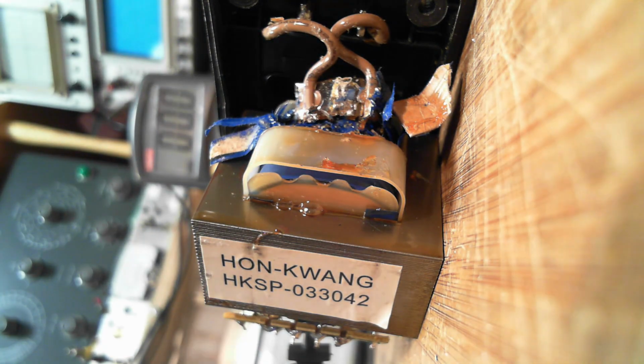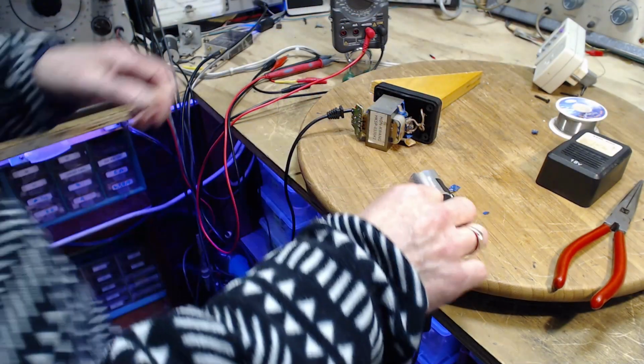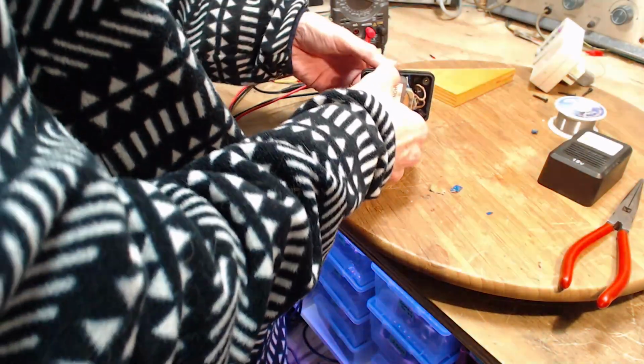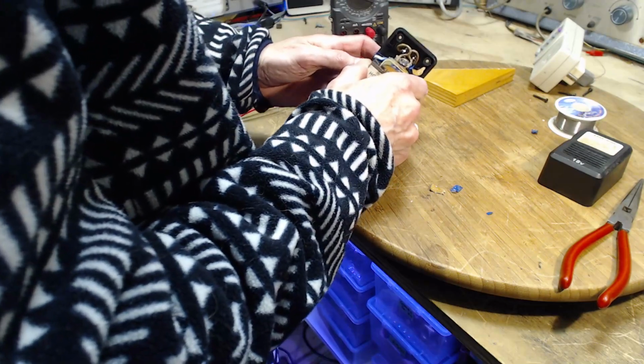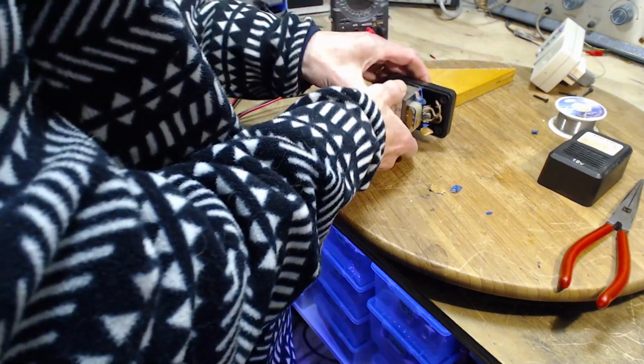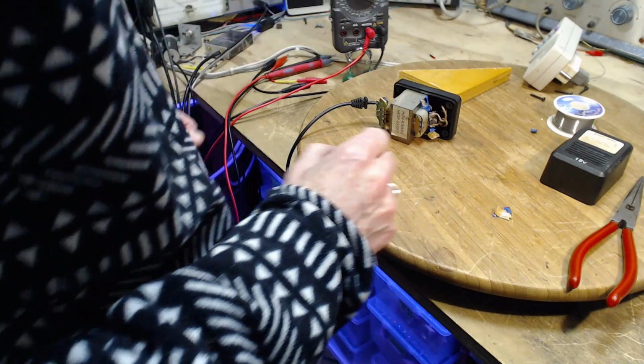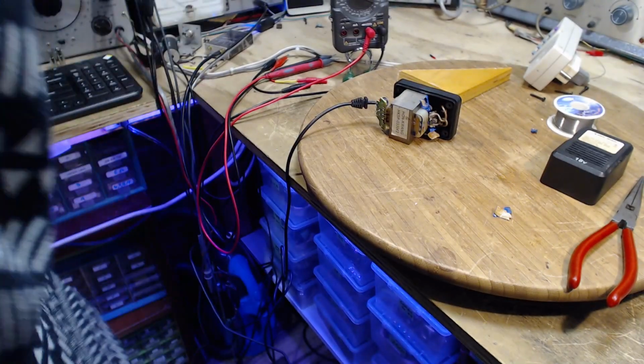Certainly ain't good enough for a test. So what can happen now is this thing can overheat, but we should see that with the dim bulbs or the current drain, or even the smoke—the smoke may clue us in that something's going wrong. But with no real load on it, this shouldn't even warm up, really—maybe a little wee bit over a long period of time.